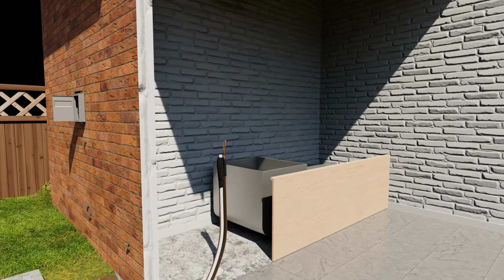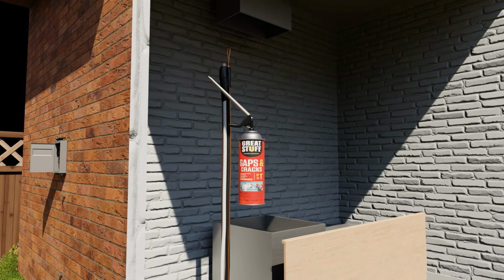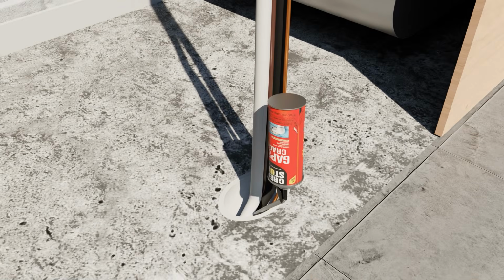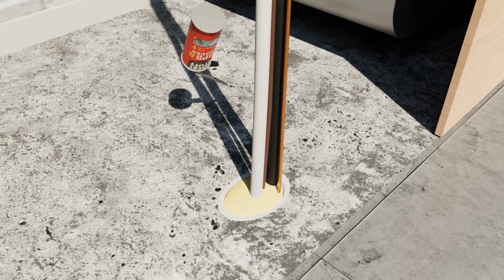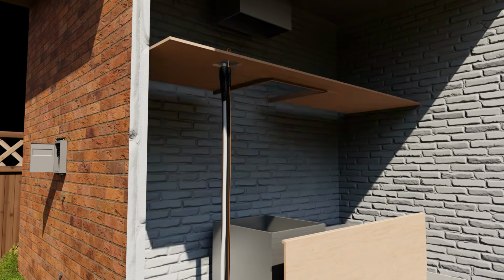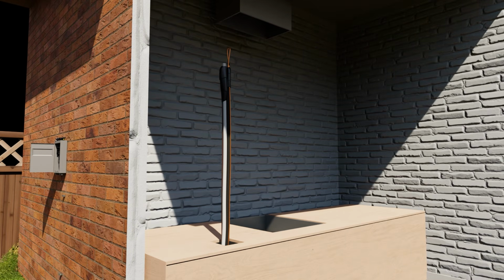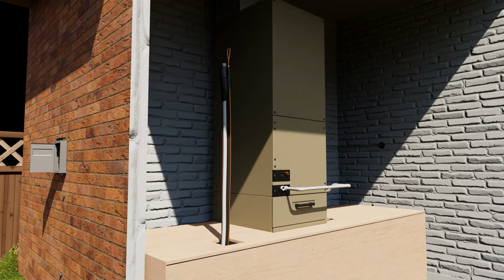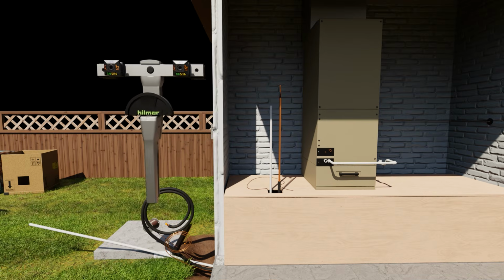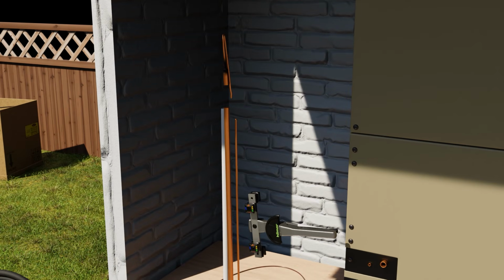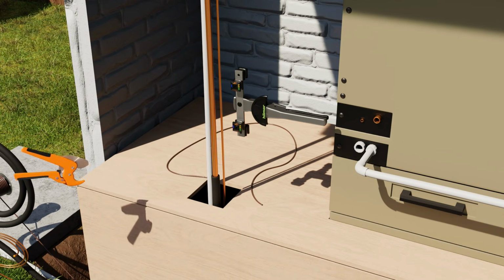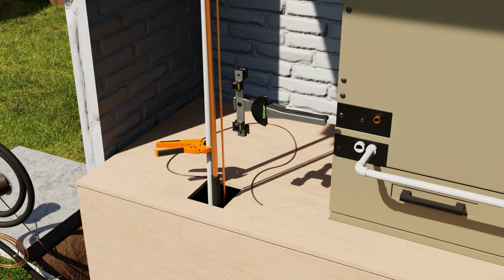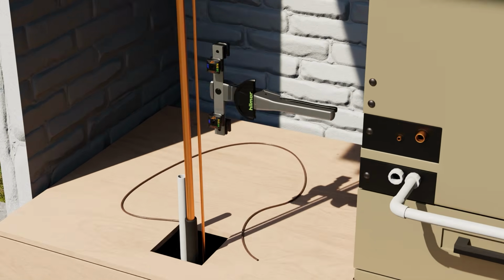Once you get more than enough excess copper, drain line, and thermostat wire above the platform, you can seal the chase. Sealing the chase is mostly just to keep insects out. It really isn't going to be completely watertight, but foam we find is generally the best policy. Next, we show placing the plywood platform top in place. This is more of an air handler installation procedure, so we're not going to focus too much on that.